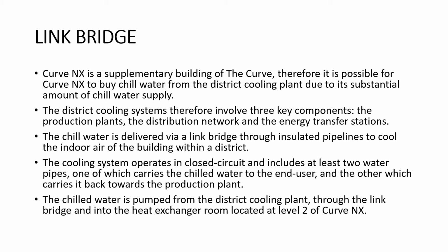The district cooling system therefore involves three key components: the production plants, the distribution network, and the energy transfer stations. So the chilled water is delivered via a link bridge through insulated pipelines to cool the indoor air of the buildings within a district. The cooling system operates in a closed circuit and includes at least two water pipes, one of which carries the chilled water to the end user, and the other which carries it back towards the production plant. So the chilled water is pumped from the district cooling plant through the link bridge and into the heat exchanger room located at level 2 of Curve NX.